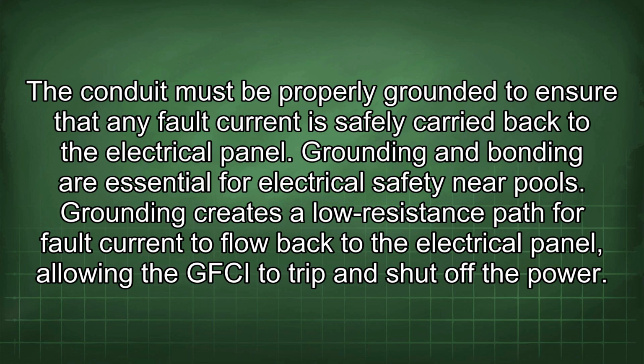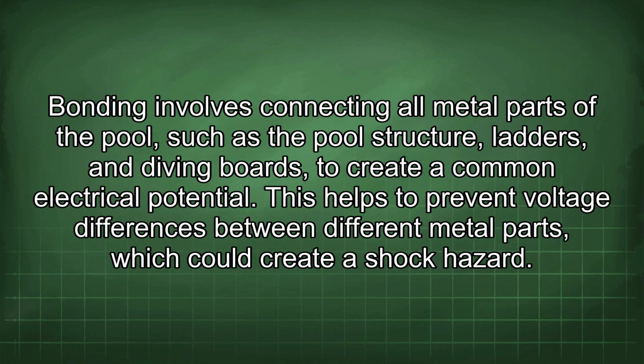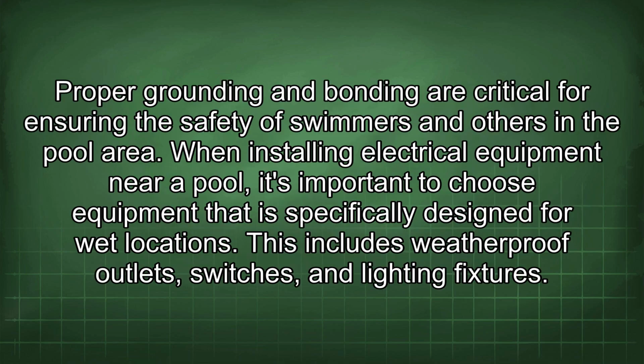Grounding and bonding are essential for electrical safety near pools. Grounding creates a low resistance path for fault current to flow back to the electrical panel, allowing the GFCI to trip and shut off the power. Bonding involves connecting all metal parts of the pool, such as the pool structure, ladders, and diving boards, to create a common electrical potential. This helps to prevent voltage differences between different metal parts, which could create a shock hazard. Proper grounding and bonding are critical for ensuring the safety of swimmers and others in the pool area.